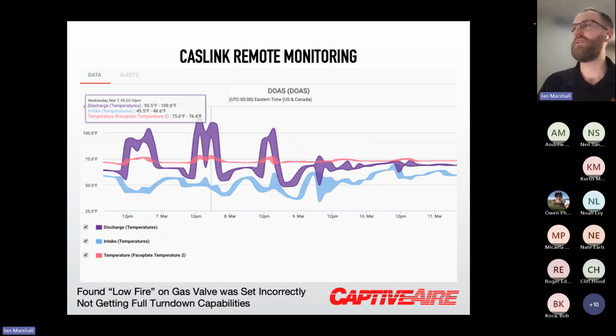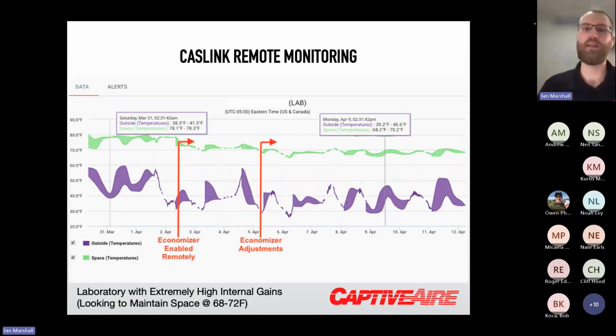So this one was every time a call for heat would come on, the discharge temperatures for that unit would spike to like 95 or 100 degrees. So we weren't getting heat modulation, which was overheating the space. So it turned out that the low fire setting on that gas valve was not set properly, so we weren't getting the modulation. Once that was resolved, we were able to get those space temperatures back into line, with the discharge temperatures not spiking.